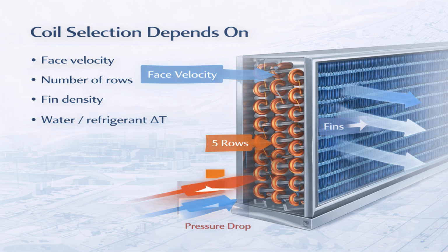When coils are poorly selected, the system may look adequate on paper. The nominal capacity may appear sufficient, but in real operation, the increased pressure drop and airflow limitations reduce the usable cooling capacity. This is why careful coil selection is essential, not just for meeting capacities, but for achieving stable airflow, proper humidification, dehumidification, acceptable noise levels, and overall system efficiency.